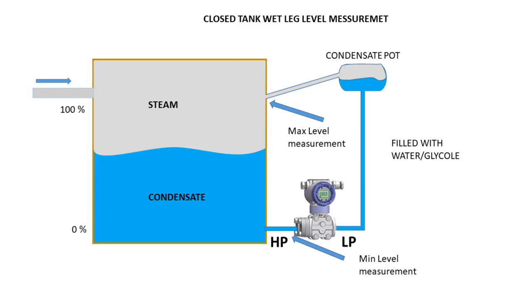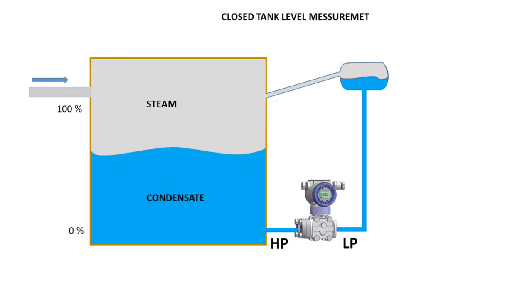If steam condenses, it will fill the low side impulse line. For this reason, we fill water in the low side and calibrate the transmitter. Let's see an example for wet leg level calculation. Assume that a tank is filled with steam. We have to measure the level using a DP level transmitter.